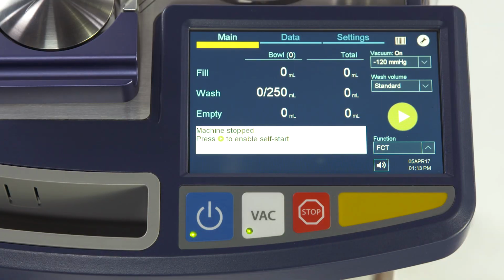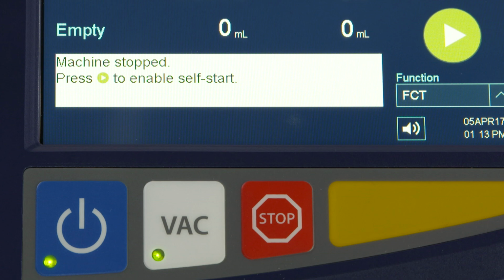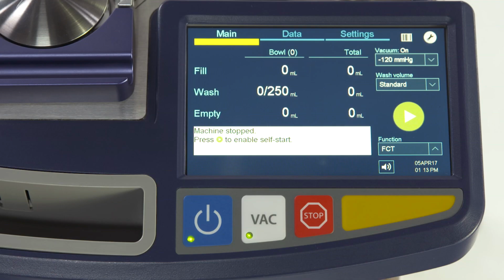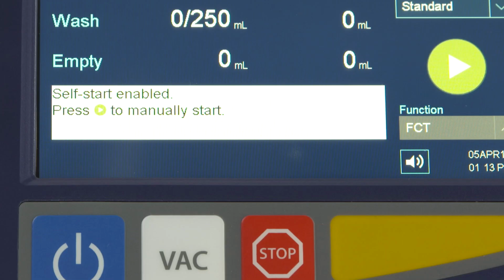Press the green button. You'll see the message, "Machine stopped." Press the green button to enable self-start. Go ahead and press the green button to activate the self-start mode. You see the message, "Self-start enabled." Press the green button to manually start.